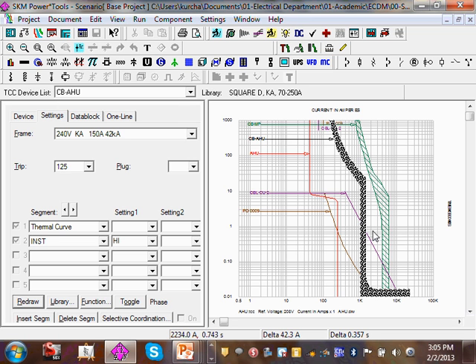So now you're standing in front of a switchgear with an arc flash, and the circuit breaker is waiting for 20 seconds before it opens. You're exposed to 20 seconds of energy. Okay? Now, how do you minimize this?